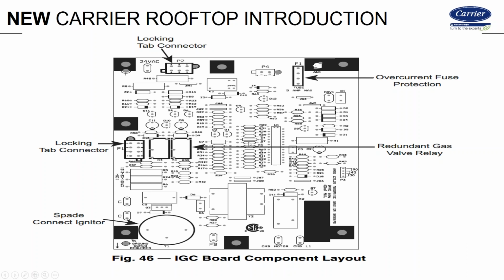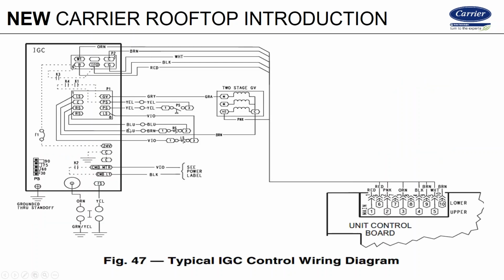This guy does a couple things. It has nothing to do with cooling whatsoever. So if you have a cooling problem, don't change your IGC board out. It's not going to fix it. The IGC board only controls the indoor fan motor in auto mode, and it controls heating functions and safeguards and has alerts for heating operation issues like limits. So that's what it does.